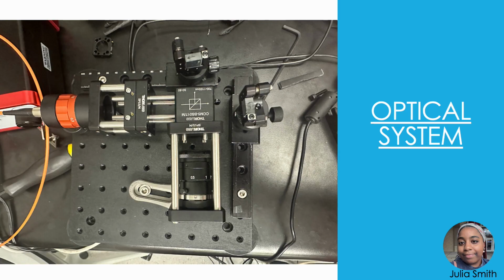So this is our optical system that we have designed for the use of being a Raman spectrometer. On the left, you can see a collimator that we have used to collimate the light from the fiber that is transmitting the laser. Next, we use a beam splitter to split the beams onto the diffraction gratings. The diffraction gratings will be tilted at the Littrow angle, which is the angle at which a wavelength is retroreflected back towards the same incident path, so all the light and the information can be collected.